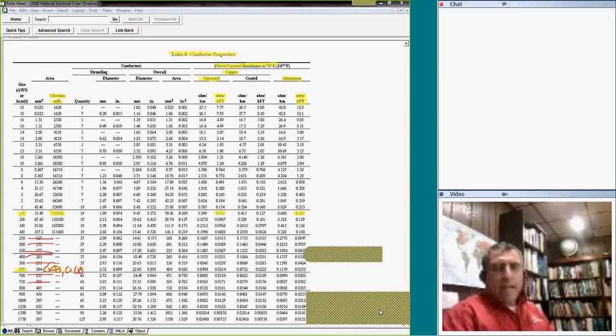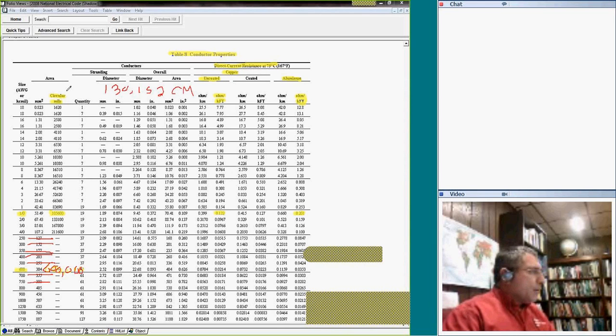Any questions about how to use this table? Something that comes up all the time. Suppose you did a calculation, a voltage drop calculation, and you came up with, let's just say, 130,152 circular mil. You came up with this value. Then come under the circular mil column and try to find the conductor that has 130,152 circular mil. Okay, let's see. Okay, let's start right here.